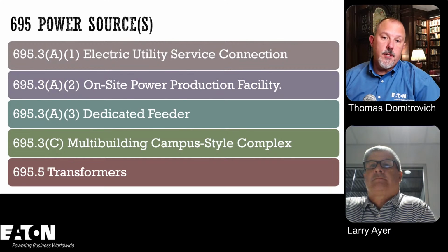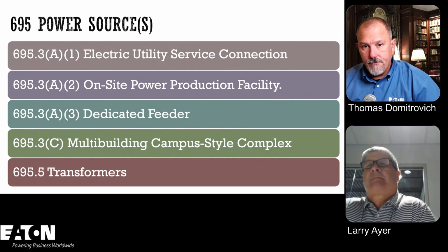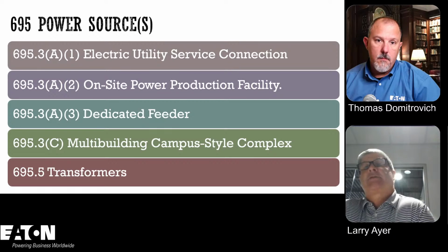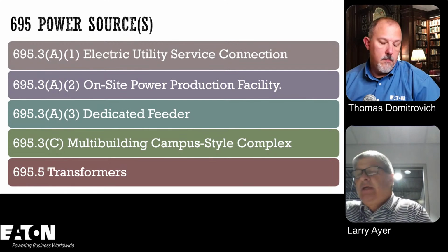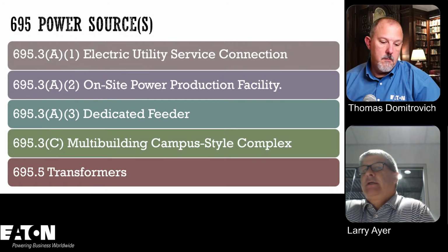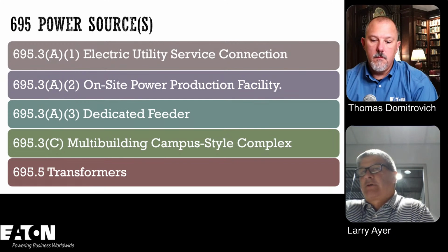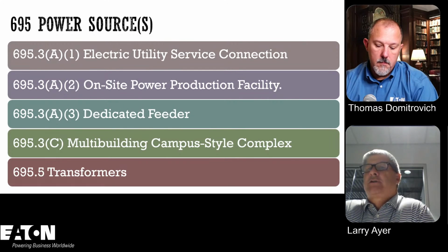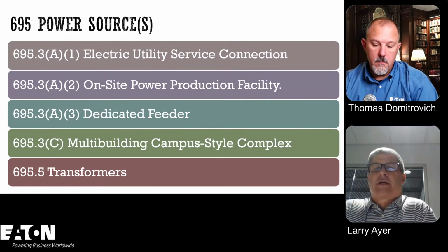Now these are your sources. You got 5 options, right? Right. So you have 5 options. And so if you look at this in 695, these things are kind of spread out, right? So we go 695.3A1, A2, and A3. So those are electric utility service connections. So that is basically taking a feed directly from the utility and going straight to the fire pump controller.